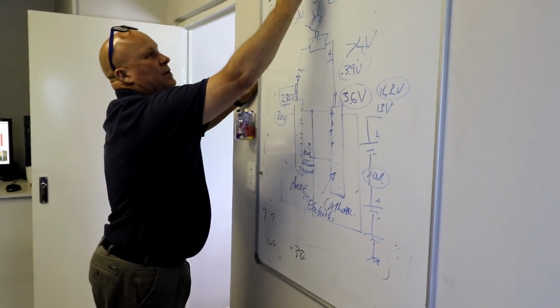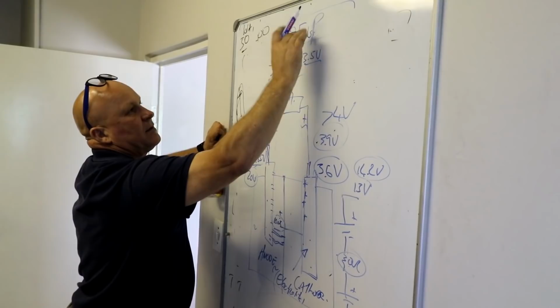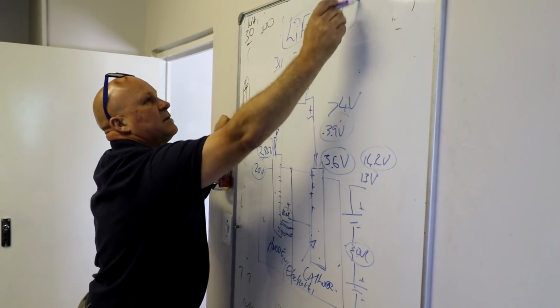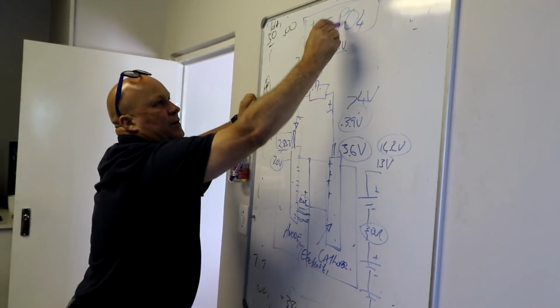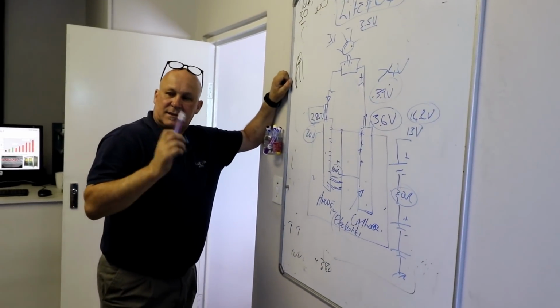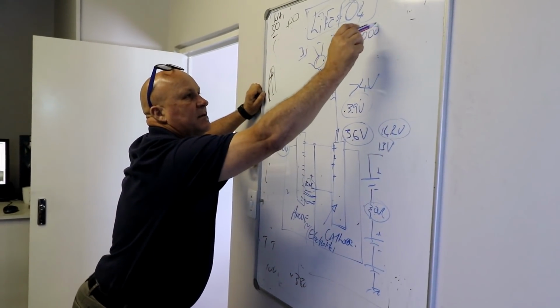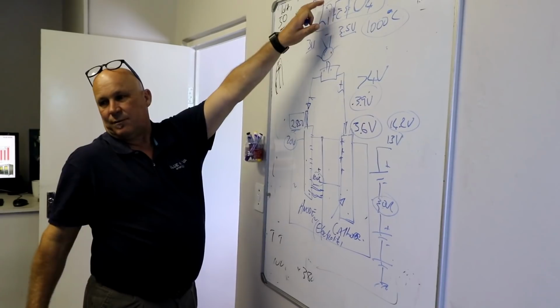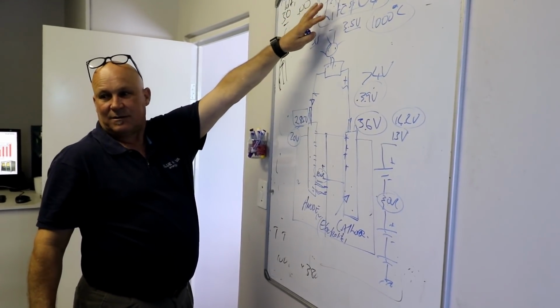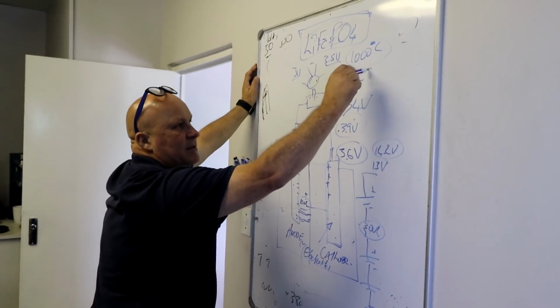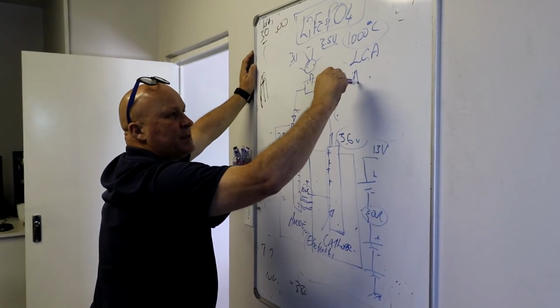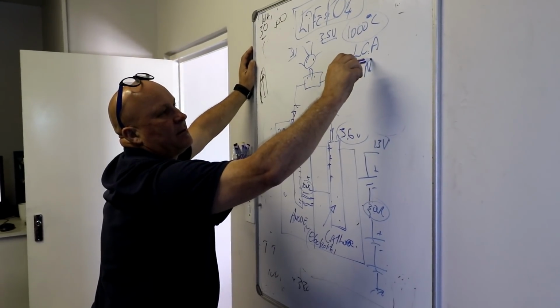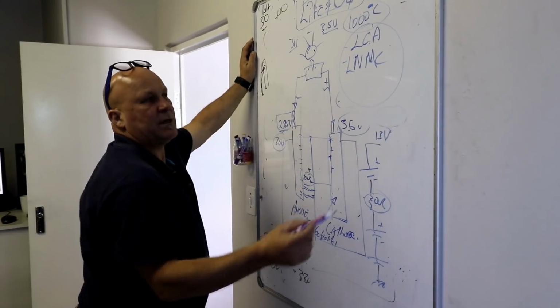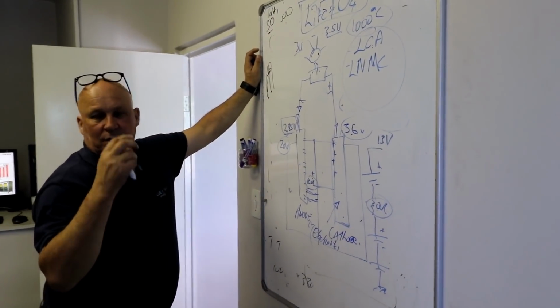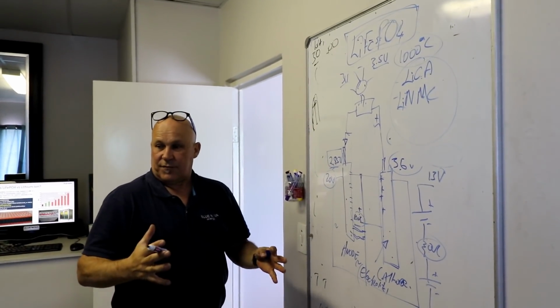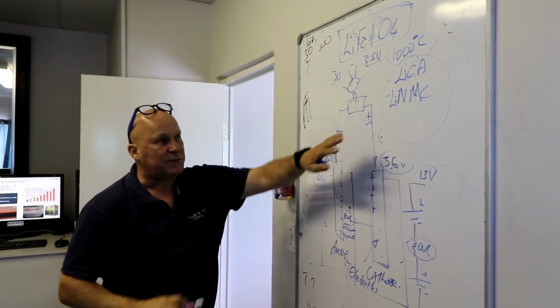We use lithium iron phosphate, LiFePO4, and this cathode material has strong bonding between the oxygen molecule and lithium, making it safe even up to 1000 degrees C. I'll show you how we can put these cells in a high temperature fire and they won't explode. But other chemistries, like lithium cobalt aluminium oxide, or NMC, lithium nickel manganese cobalt, have weaker bonding between the oxygen and lithium molecules, so if it comes off, it starts burning violently - that's what's been seen historically.